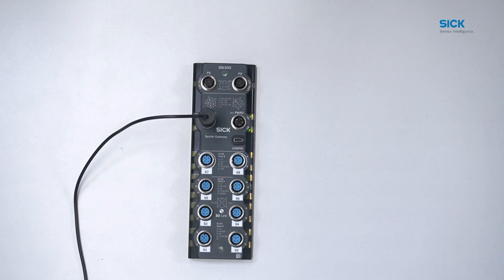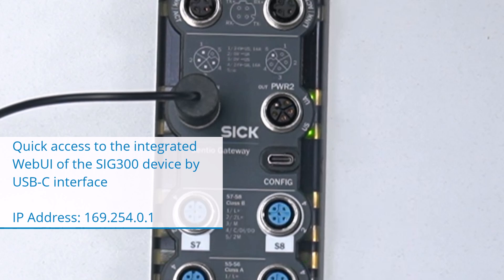Beneath the power output port of the SIG300, we also have a USB-C interface marked with CONFIG. This configuration port enables quick access to the integrated web user interface on the device. To access the web UI of the SIG300, connect your PC or laptop to the USB-C interface and enter the default IP address into your web browser.